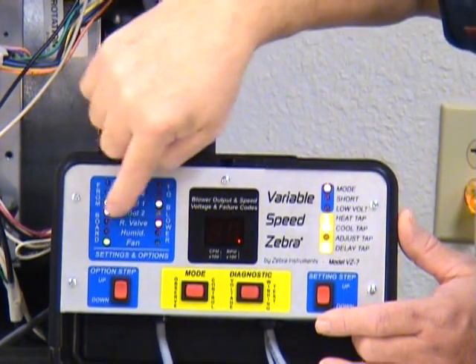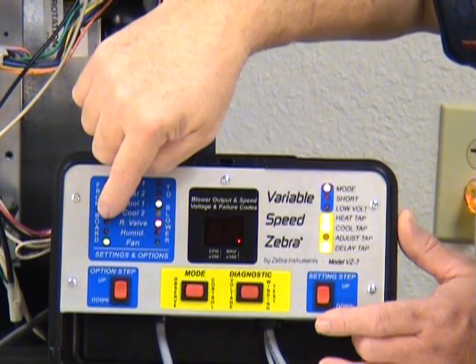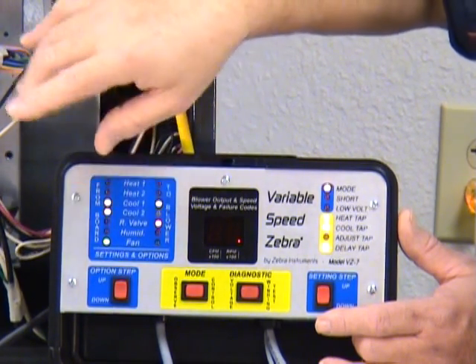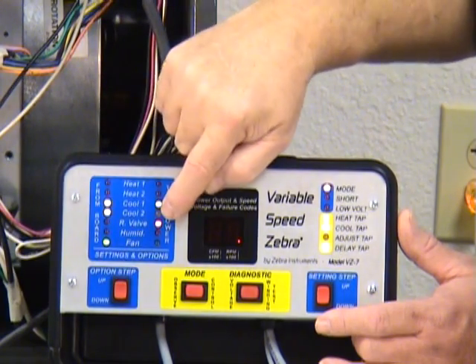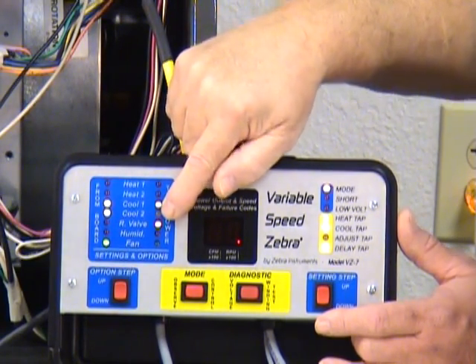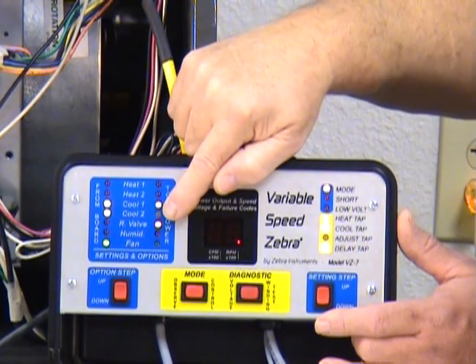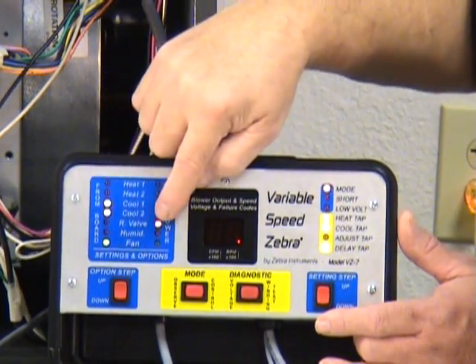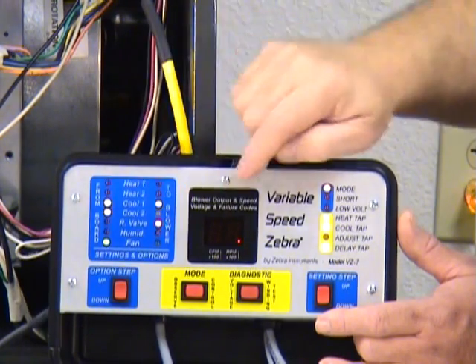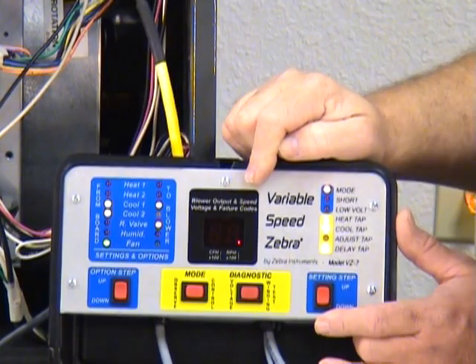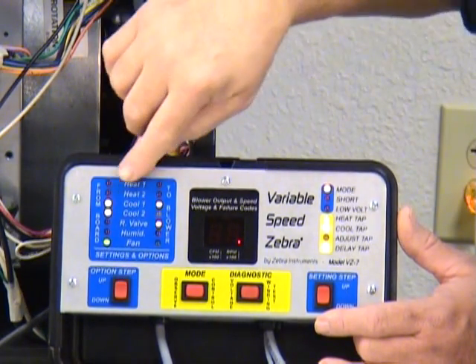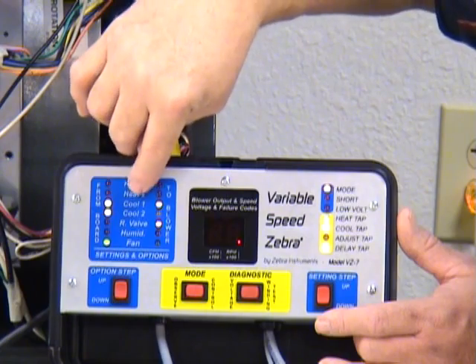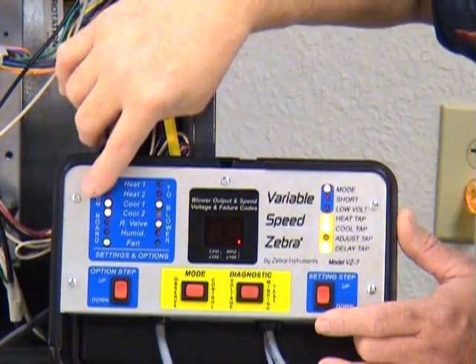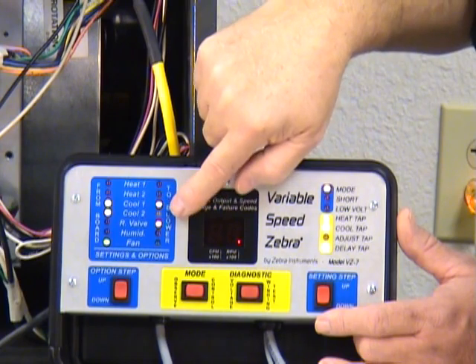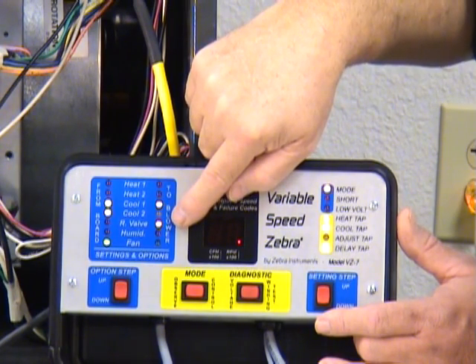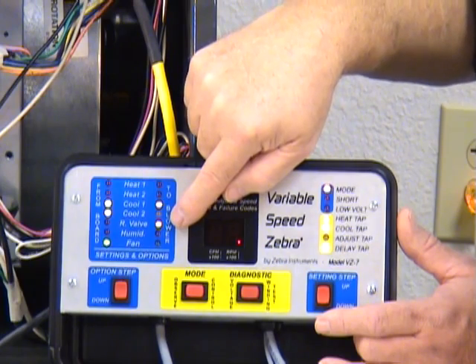If your system was actually hooked up and you had a reversing valve on there, it probably would be receiving that signal. This light doesn't mean it's sending a signal to it. What it means is that it's telling the motor that the reversing valve has been activated. In many systems, if you are running a heat pump, that means the motor should slow down a little bit because it's in the heating mode as compared to the cooling mode. So in a heat pump system, these two lines, the heat 1 and the heat 2, you'll probably never see them come on. What you'll see is the two cooling stages and/or the reversing valve line, indicating that the heat pump is being activated in that mode.